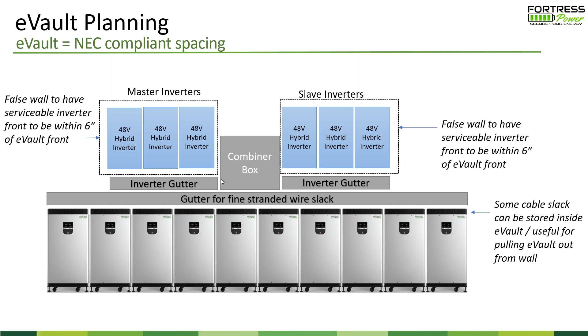Larger commercial size battery projects are kind of the future, especially in regions with high commercial demand rate structures - that's often the most cost-effective use of batteries for commercial demand management. One thing to keep in mind: when designing systems for 3-phase Sol-Ark Fortress systems, you'll want to group your Sol-Arks into groups of 3. There is a specialty case where you could have just 2 Sol-Arks on 3-phase, but I'd defer to Sol-Ark for guidance on the backup capabilities of that type of system.